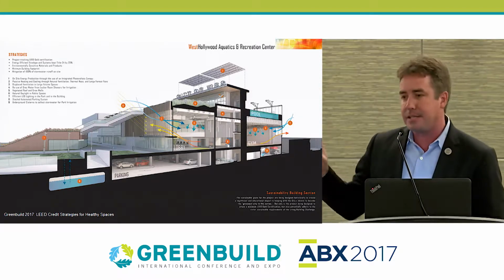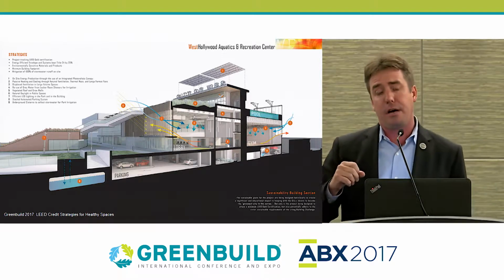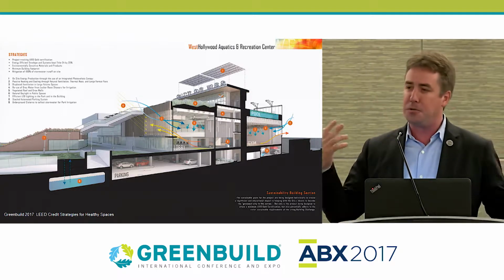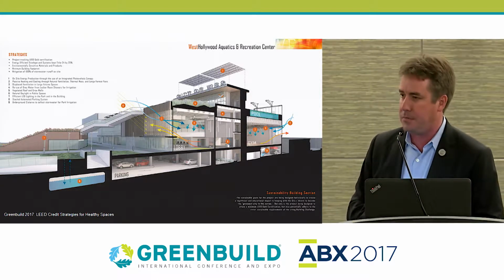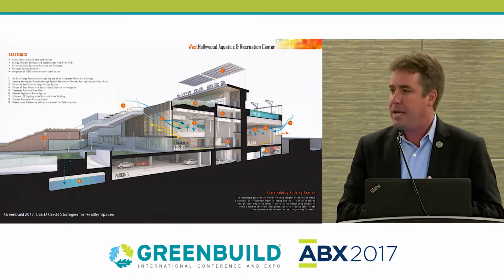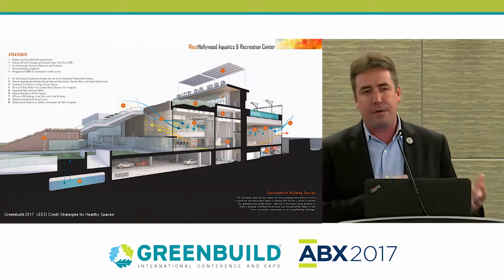But there are some ancillary HVAC systems. There's a parking office down on the lower level, and a small lifeguard office up on the pool deck that have little 200 CFM fan coil units serving them. Introducing an outdoor air monitoring device into such a small piece of equipment is not a standard option. It's not a custom piece of equipment. That's technically a difficult thing to do.